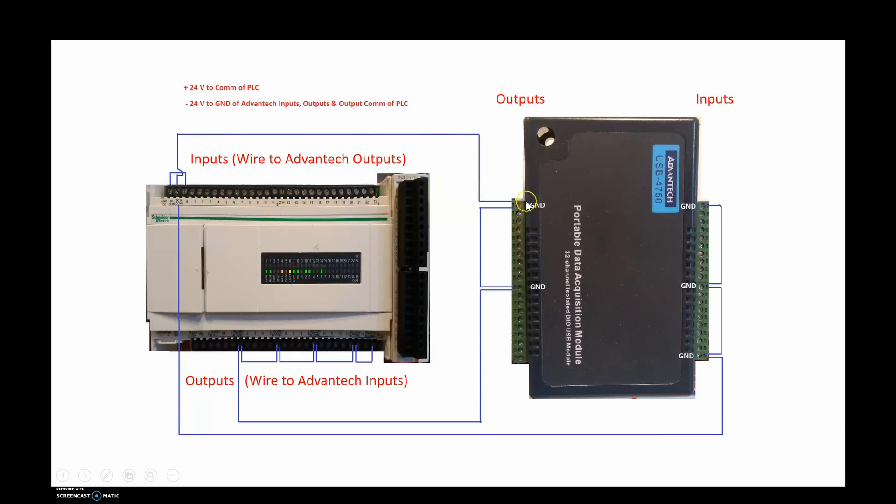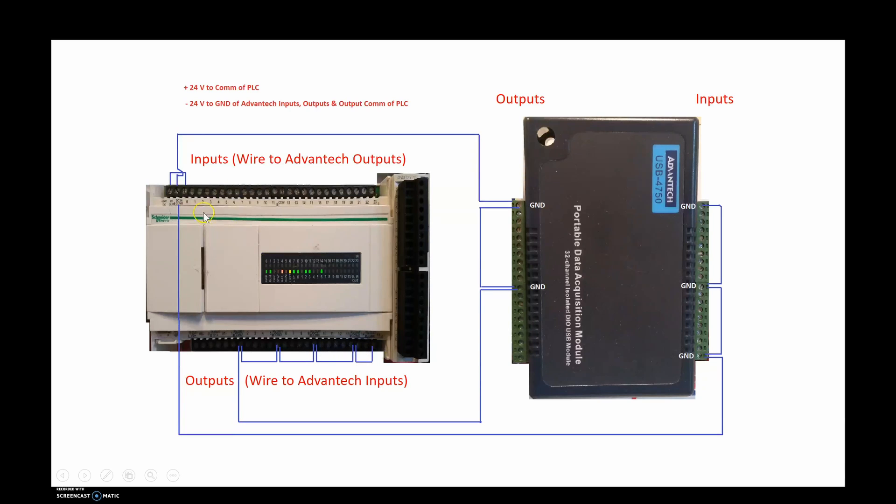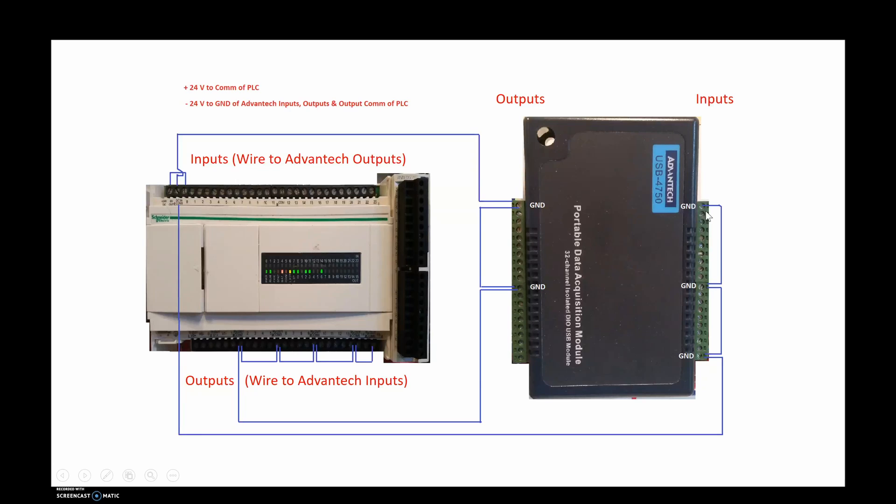The negative ties over here to all the grounds on the output side. It ties into the commons on all of your outputs of your PLC. And the negative also goes over and ties into the grounds of all of your inputs on the Advantech 4750. As long as you've got this wiring, then everything should work properly.